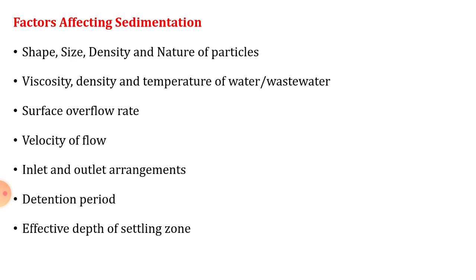There are different factors which affect sedimentation and should be considered while deciding the sedimentation tank. First is shape, size, density and nature of particle. Viscosity, density and temperature of water or wastewater. Surface overflow rate, velocity of flow, inlet and outlet arrangement, detention period, effective depth of the settling zone and all.